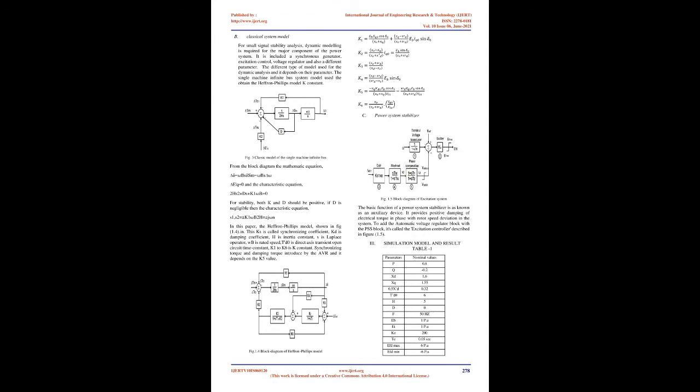Synchronizing torque and damping torque introduced by the AVR depend on the K5 value. Fig 1.4 block diagram of Heffron-Phillips model. Fig 1.5 block diagram of excitation system. The basic function of a power system stabilizer (PSS) is as an auxiliary device — it provides positive damping of electrical torque in phase with rotor speed deviation. Adding the automatic voltage regulator block with a PSS block is called the excitation controller, described in Figure 1.5.